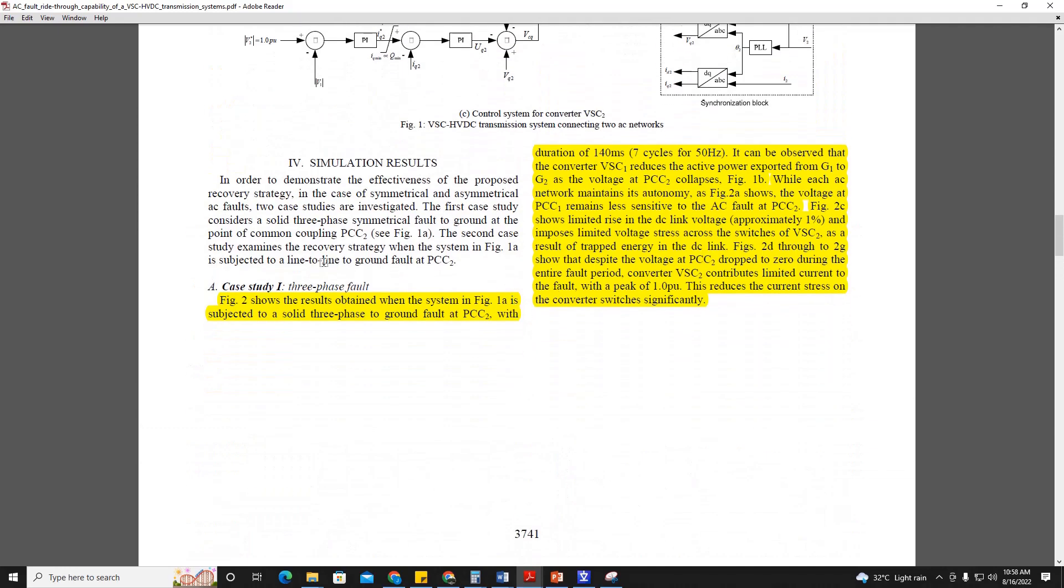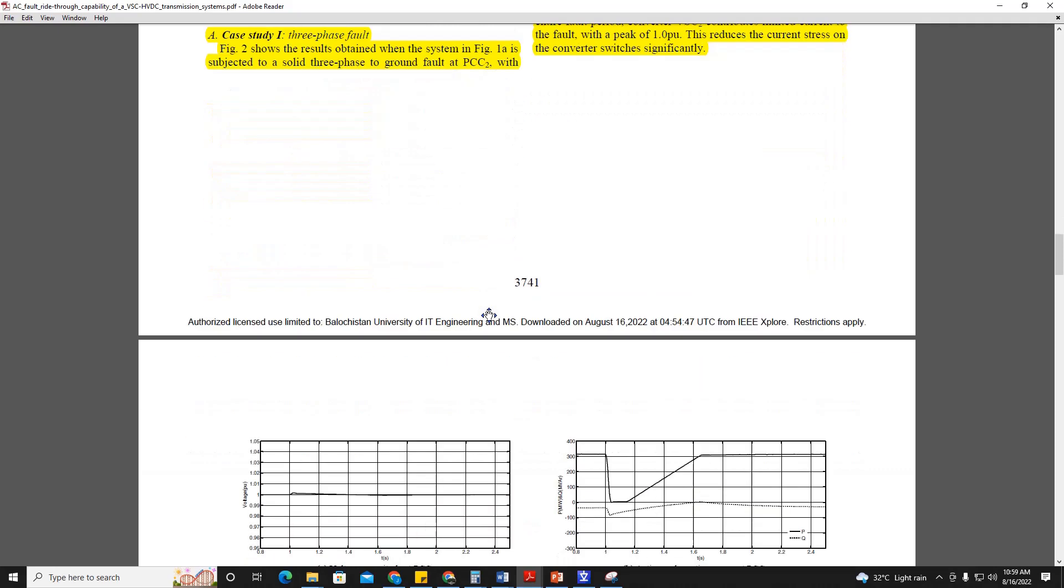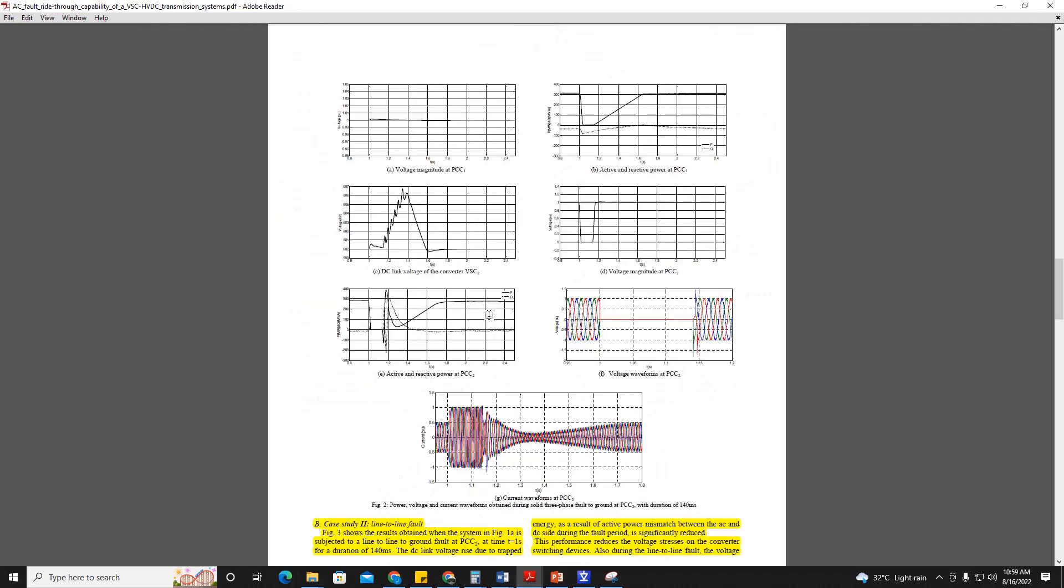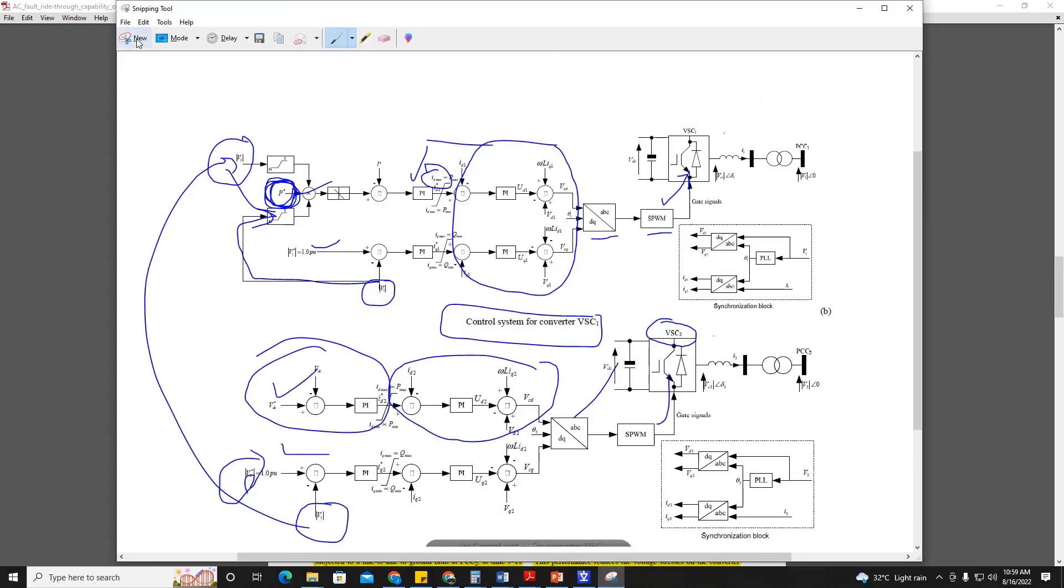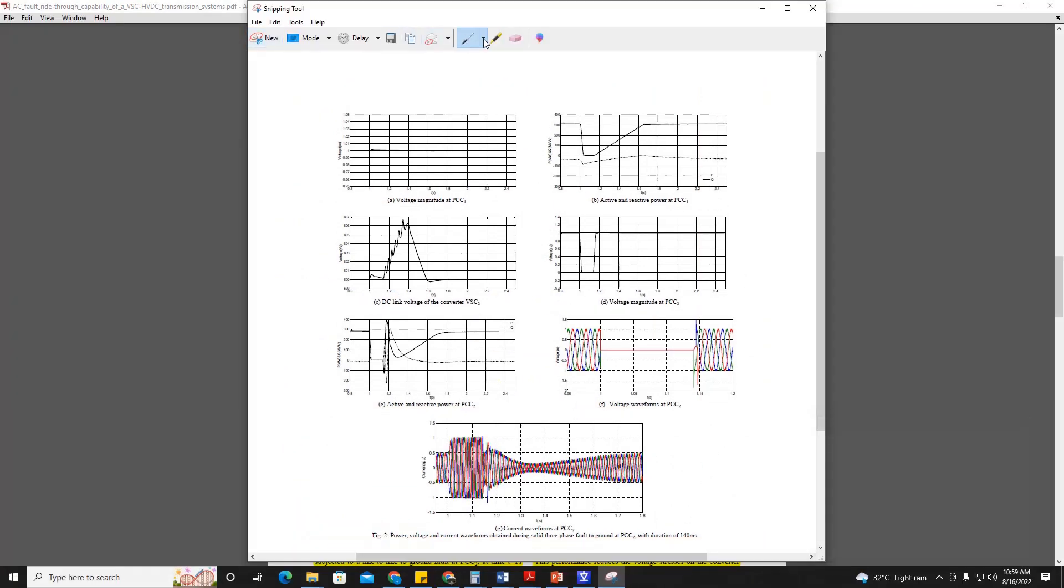Let's discuss simulation results. Case 1 is the three-phase fault which is more critical than case 2. The fault is for 7 cycles, 50 Hz, 140 ms. You can see here that the fault is happening at grid 2 and due to the three-phase fault, this voltage dip occurs. There is voltage dip and voltage interruption, zero voltage here.